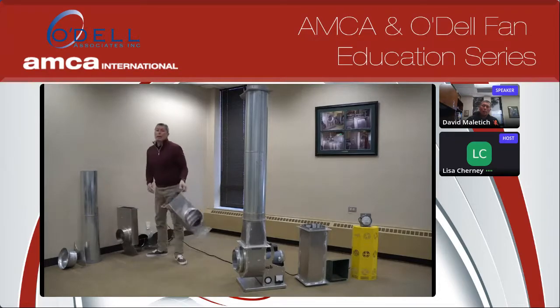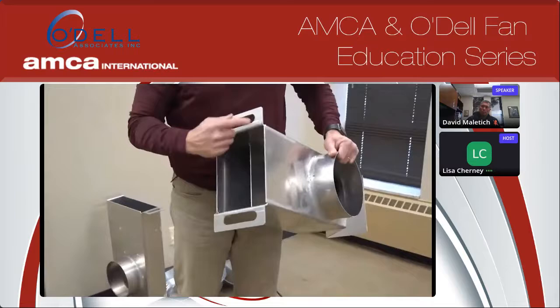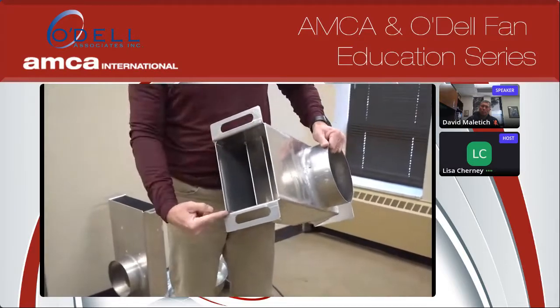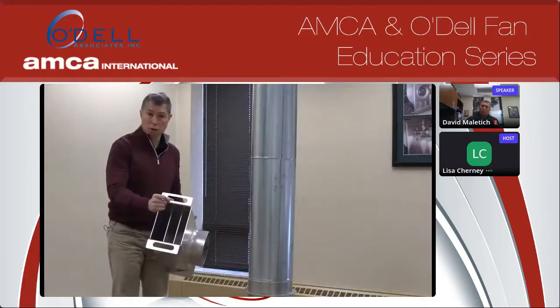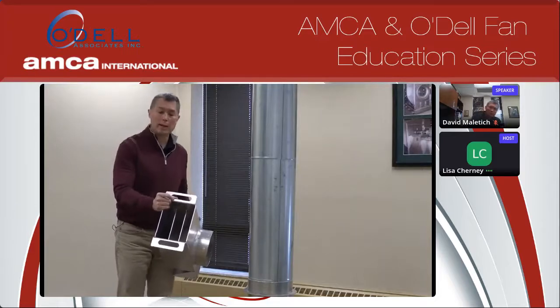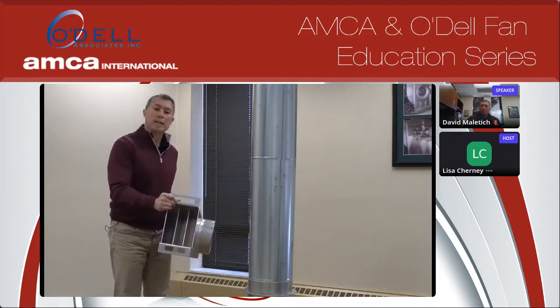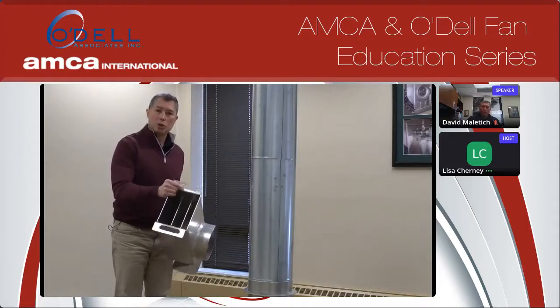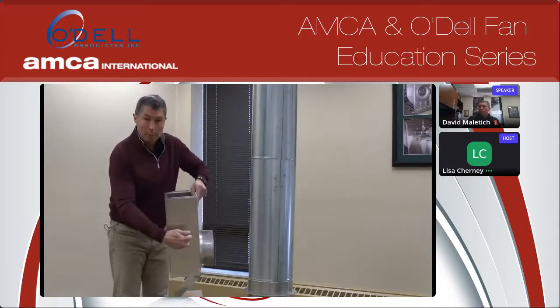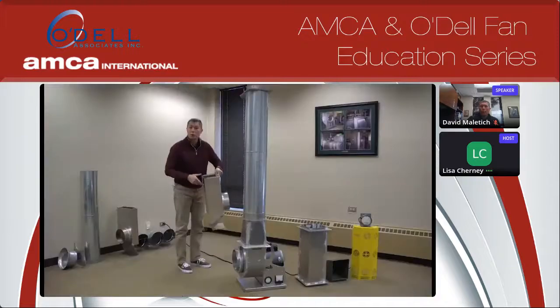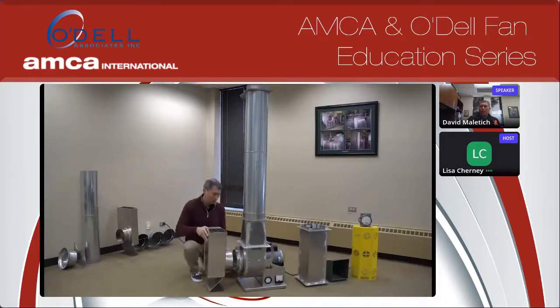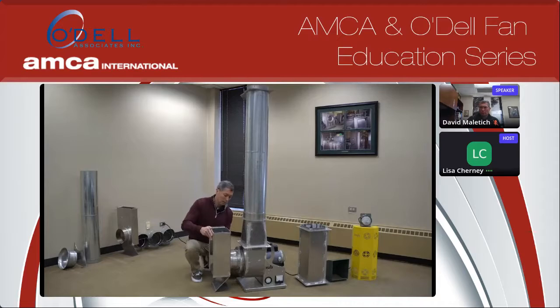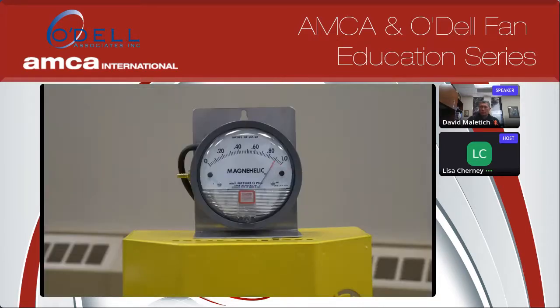Now here we have an inlet box that's a little bit better designed. Its aspect ratio is much more square. Its depth compared to its width is much more on the square side of things. It's not an elongated rectangle. The other thing you'll notice is that we've added turning vanes to this inlet box. Turning vanes, just like with the 90-degree elbow, help efficiently load the air as it goes into the fan. Put this onto the inlet of the fan, and you'll notice that, yes, we do have a loss associated with the inlet box, but it's much less than the improperly designed inlet box losses.